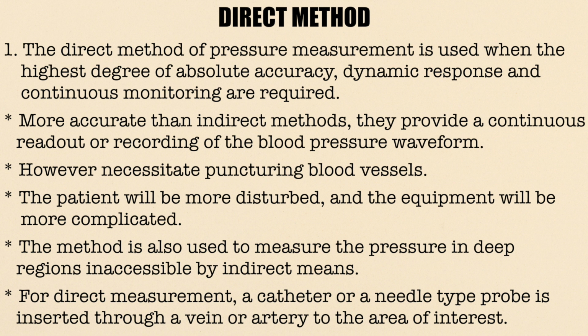They provide a continuous readout or recording of the blood pressure waveform. However, direct methods necessitate puncturing of blood vessels. The patient will be more disturbed and the equipment will be more complicated. The direct method is also used to measure the pressure in deep regions inaccessible by indirect means.